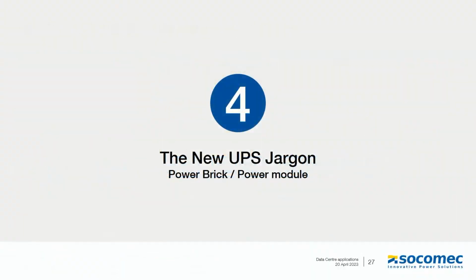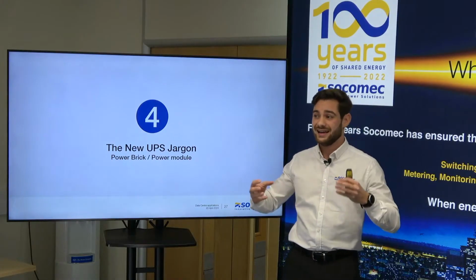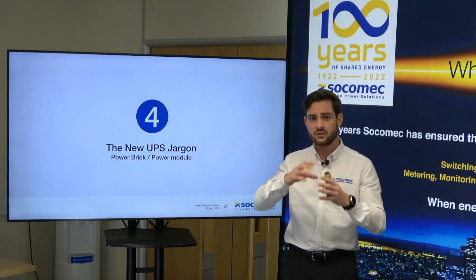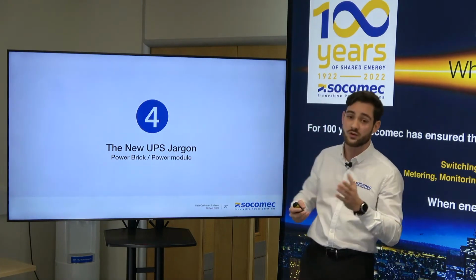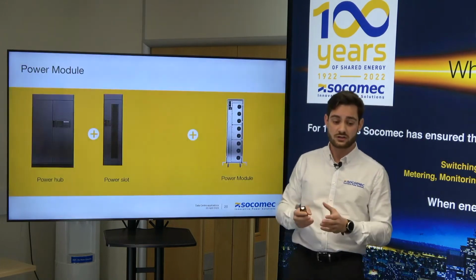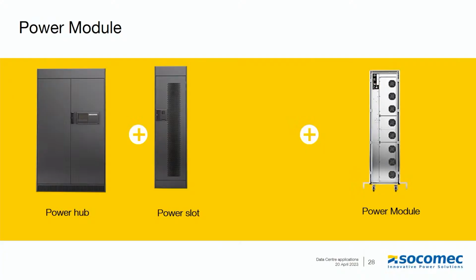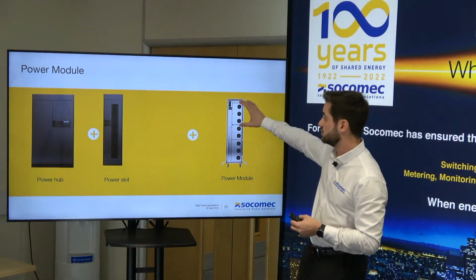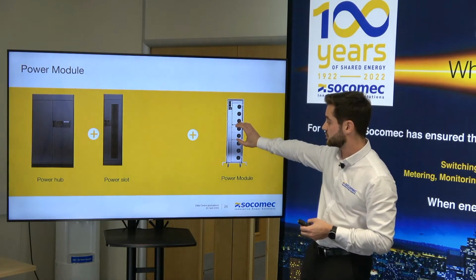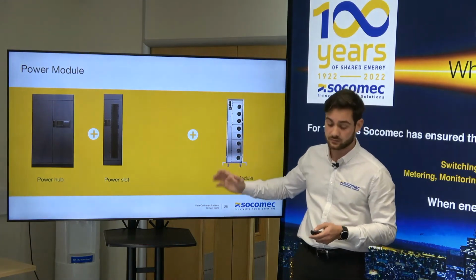The UPS jargon. So we hear a lot about power bricks, power modules, and it can be confusing if it's for monolithic or modular UPS. And there is a bit of crossed wires around that. So we need to put some words on the right products. So first of all, the power module. We can think about a modular UPS system made of 3 parts: power hub, power slot, and then power module. The power module is composed of 3 components. So at the top you would get the rectifier, in the middle the battery charger, and then at the bottom the inverter.